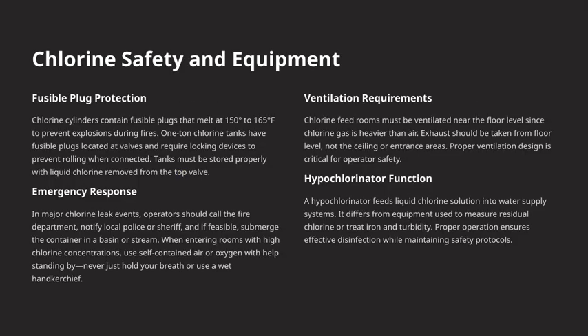Now, let's talk about chlorine safety and equipment. First, fusible plug protection plays a critical role. Chlorine cylinders are equipped with fusible plugs that melt between 150 and 165 degrees Fahrenheit. This melting acts as a safety mechanism to prevent explosions during a fire. For larger tanks, like the 1-ton cylinders, the fusible plugs are located at the valves and need to be secured with locking devices to prevent the tanks from rolling when connected. It's also essential to store these tanks properly, ensuring that any liquid chlorine is removed from the top valve to reduce risks.